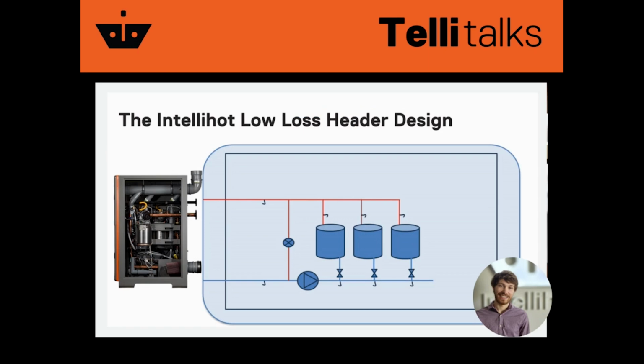Intellihot has a patented low-loss header design. A low-loss header is a concept that's applied primarily in the hydronics world. It is a method upon which you can use hydraulic separation to mitigate pressure drop. And that's a lot of words, but essentially what it means is that in a low-loss header, you do not force all of your flow rate through your restriction.